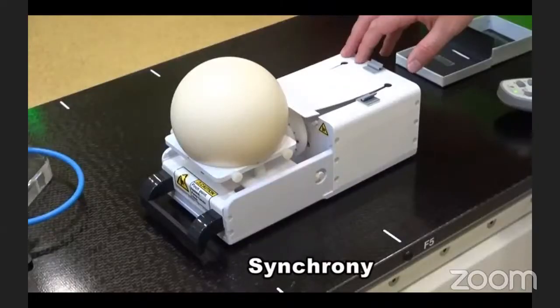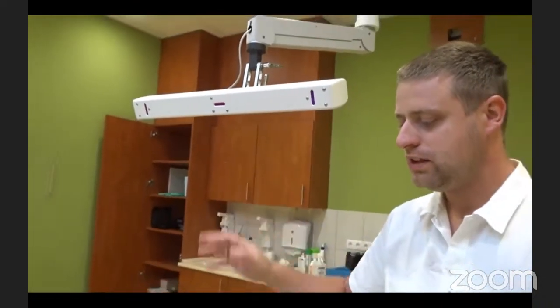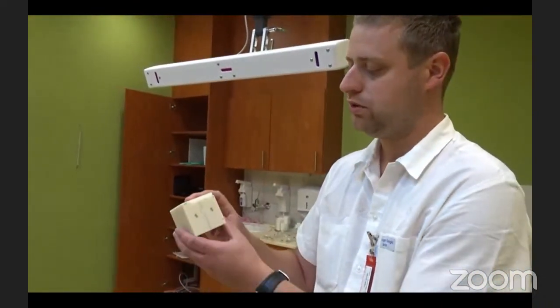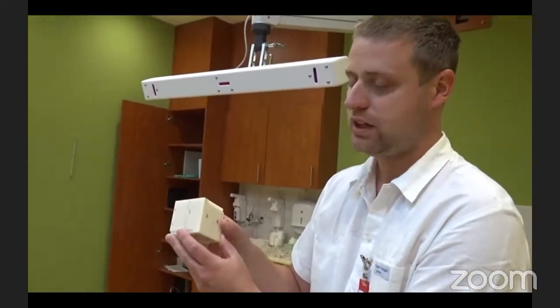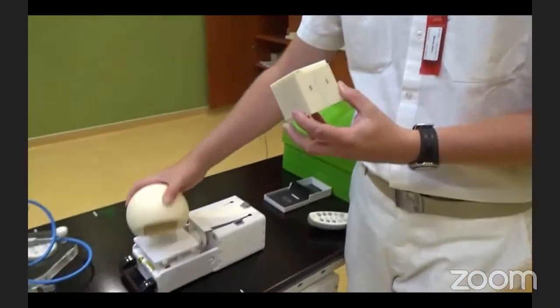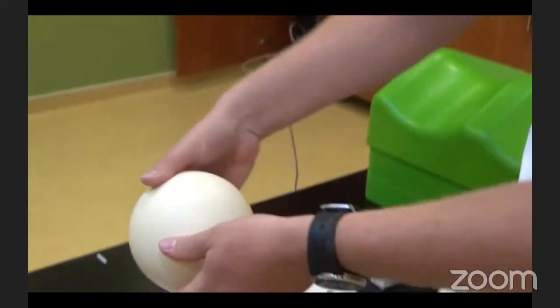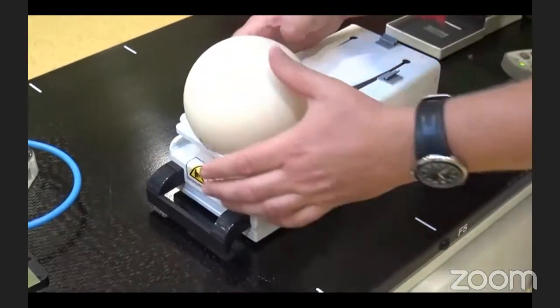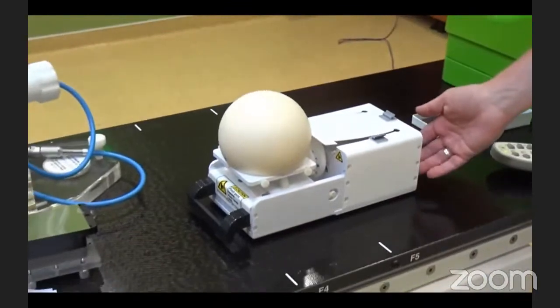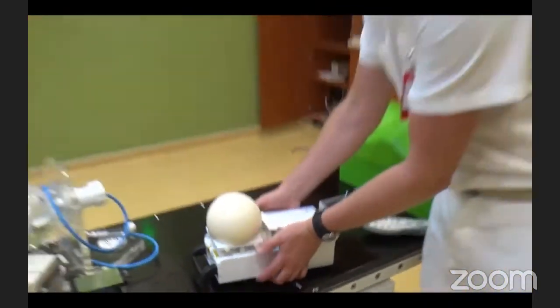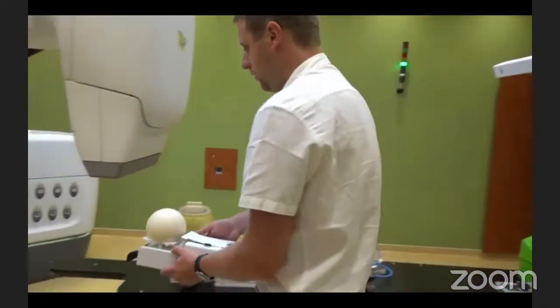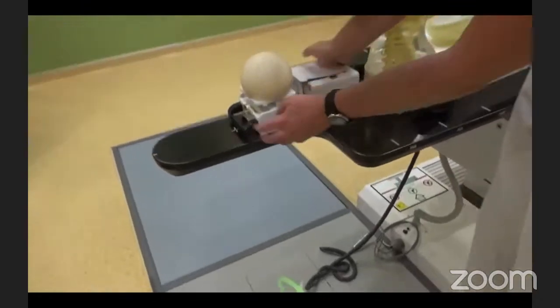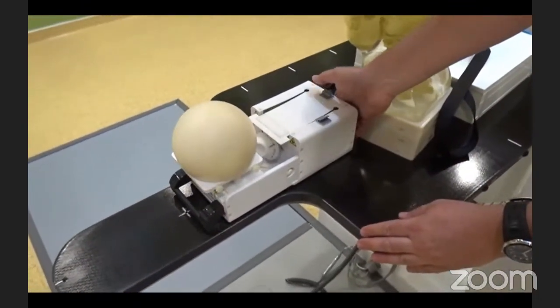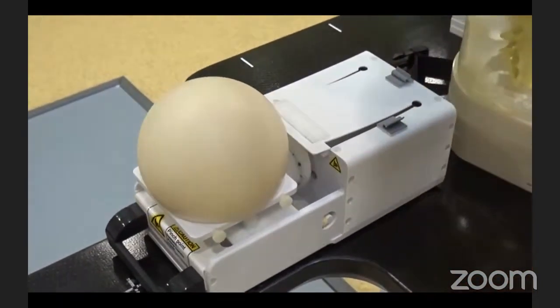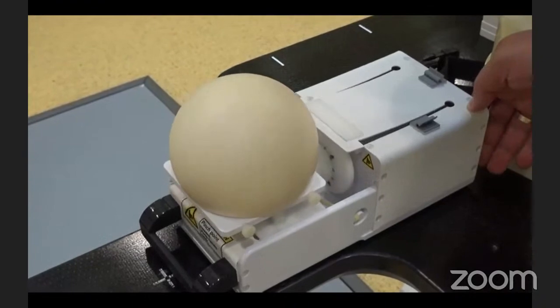As I showed in my presentation, the CyberKnife has a motion tracking option, the Synchrony with the Synchrony camera, and this phantom is dedicated to the tracking motion, the checking of the tracking delivery. We are using the same ball cube insert and placing it into this sphere, and we are positioning it on this moving phantom. We put it under the accelerator and simulate the breathing cycle of the patient, and we are measuring the total targeting error while the target is moving.